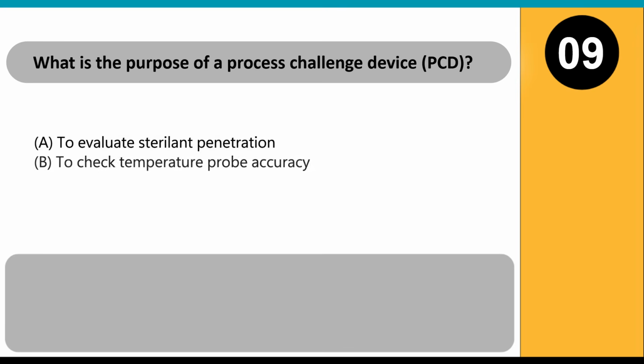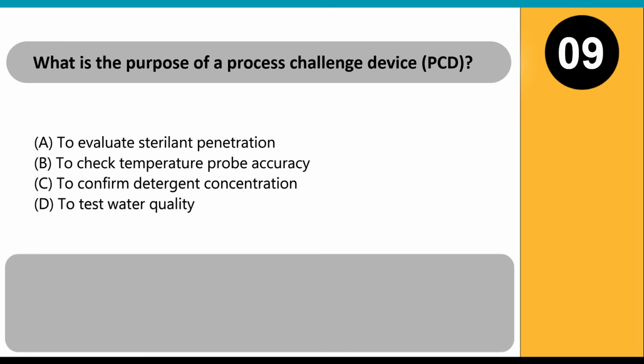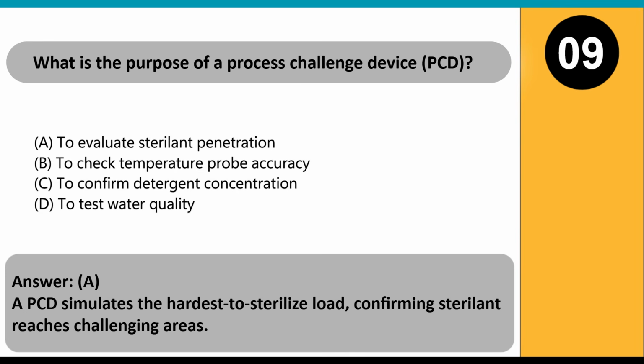What is the purpose of a process challenge device, PCD? A. To evaluate sterilant penetration. B. To check temperature probe accuracy. C. To confirm detergent concentration. D. To test water quality. Answer A. A PCD simulates the hardest to sterilize load, confirming sterilant reaches challenging areas.